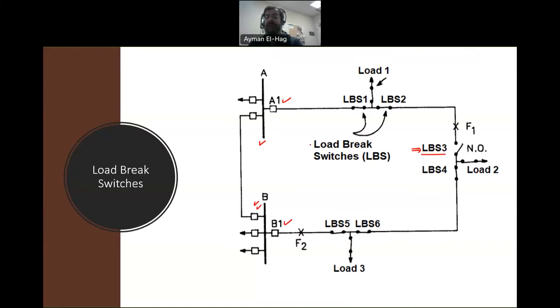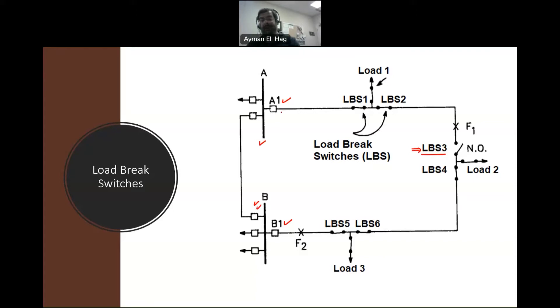Why do we open the ring system? Because it is much easier to coordinate the protection system when a fault happens. In a closed ring it would be very hard to coordinate which breaker opens first and which acts as backup. With a radial system, power flows from bus A to load 1, and from bus B to loads 2 and 3. If a fault occurs on one feeder, only that feeder's breaker is responsible — there is no coordination problem.